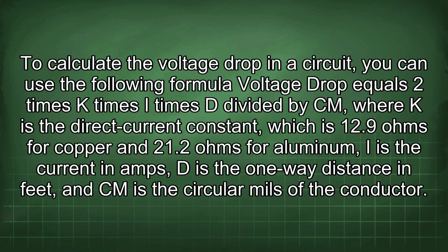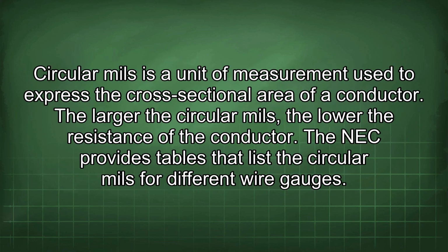I is the current in amps, D is the one-way distance in feet, and Cm is the circular mils of the conductor. Circular mils is a unit of measurement used to express the cross-sectional area of a conductor. The larger the circular mils, the lower the resistance of the conductor. The NEC provides tables that list the circular mils for different wire gauges.